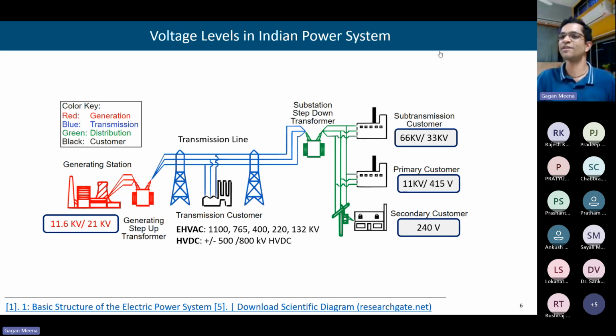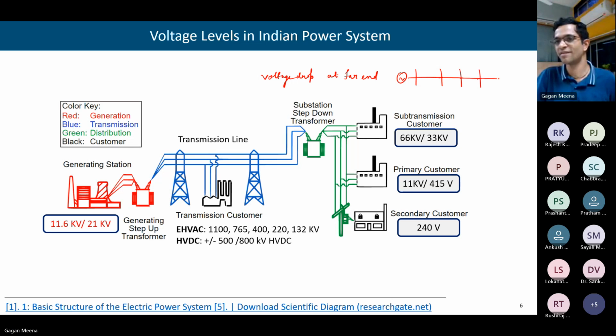There are issues; earlier we were only concerned about the voltage drop issue at the far end of the feeder. If we have a substation and several feeders, there can be laterals also. These are the laterals, and this is the far end, the last node of this main feeder. We were concerned about the voltage at this, let's say the nth bus, Vn, near the substation. We were concerned about the voltage drop at this last node, the nth node.